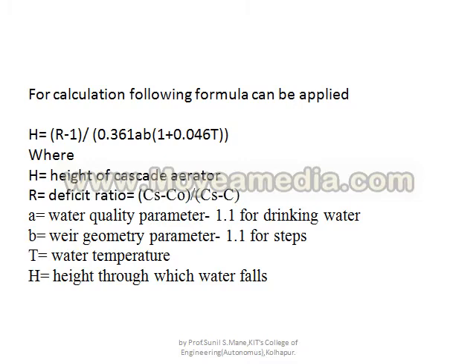B is the weir geometry parameter, which is 1.1 for steps. Various geometries exist — trays, sprays, and others — but for the cascade aerator with steps, B = 1.1. T is the water temperature; for design purposes we take T = 20°C, which is the minimum. H is the height through which the water falls.